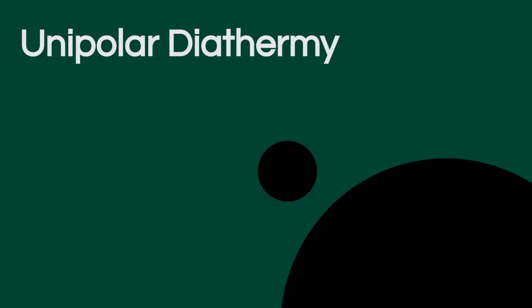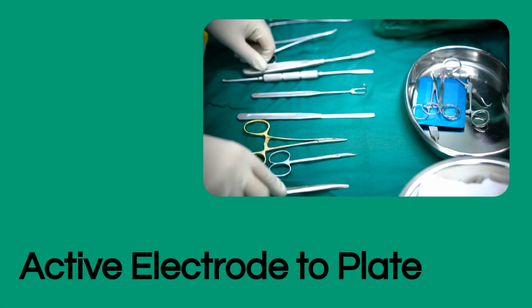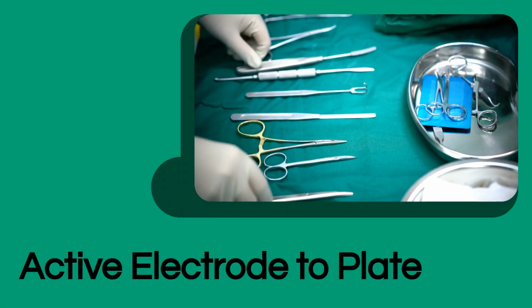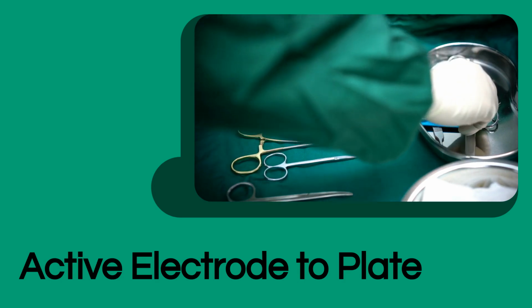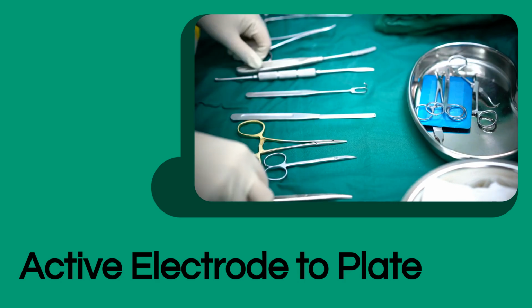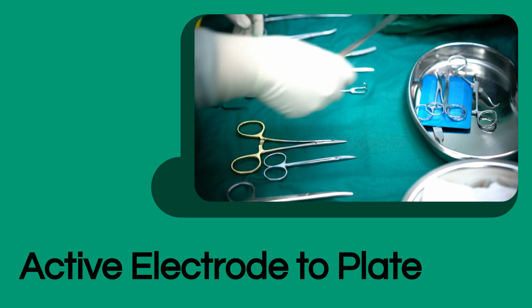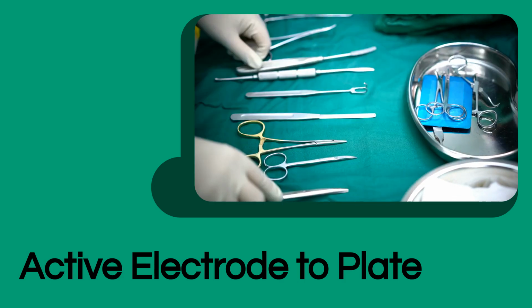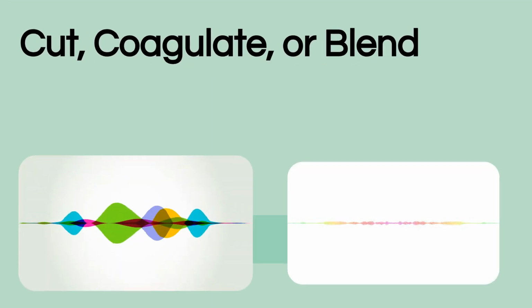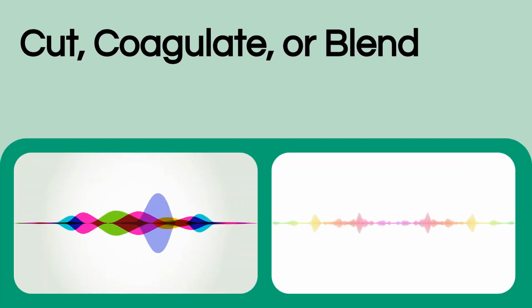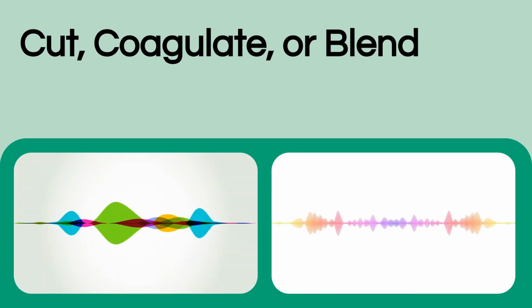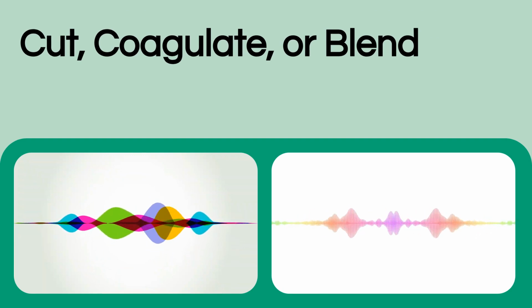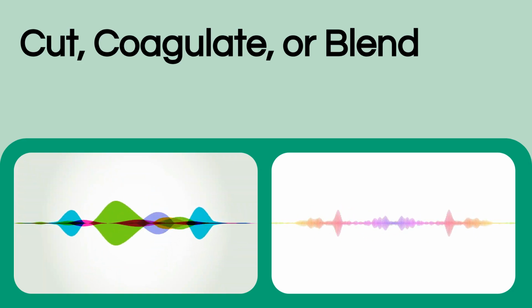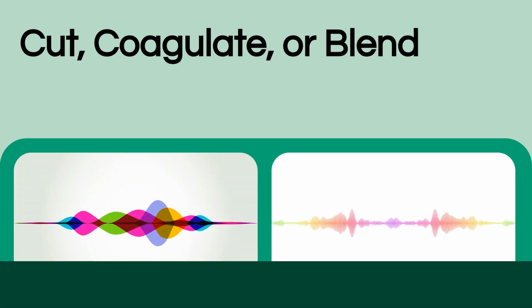Let's look at the first main type, unipolar or monopolar diathermy. In this setup, the current flows from the active electrode through the patient's body to a large return electrode or patient plate, and then back to the machine. This large plate disperses the current safely. Unipolar diathermy has various modes. The cut mode uses a continuous sine wave, while coagulate uses an interrupted high voltage wave. Blended combines both for simultaneous cutting and stopping blood flow.